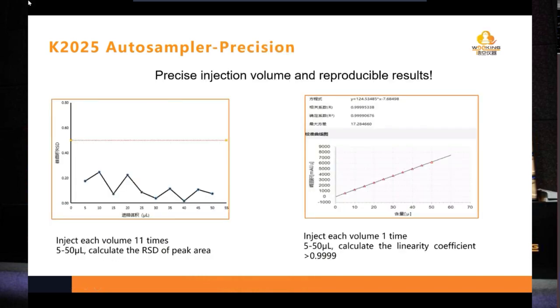The precision of the autosampler is guaranteed by reliable designs and parts. And we did several tests for the precision performance. The picture on the left shows we have a perfect precision when samples are injected 11 times. And the relative standard deviation of peak area is calculated, and all the RSDs are below 0.5%. And average injection volume from 5 to 50 microliters. And the picture on the right shows the autosampler has a good linearity when every injection volume is injected only one time. We have the linearity coefficient.